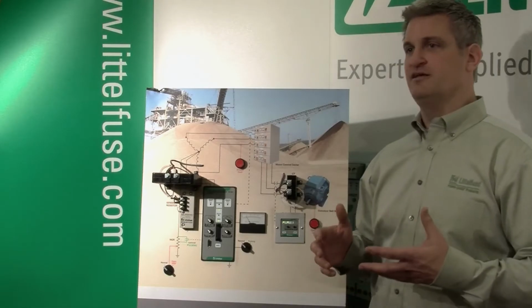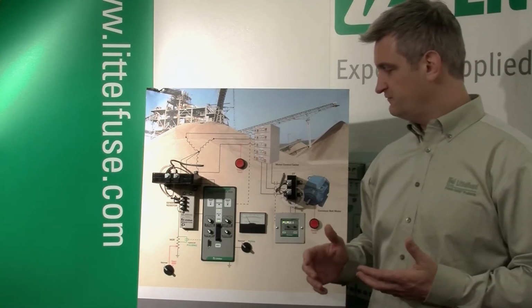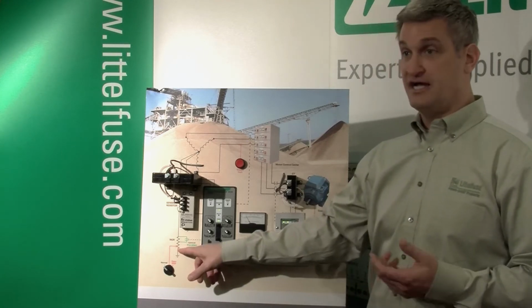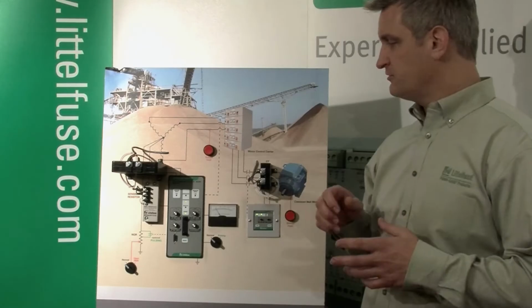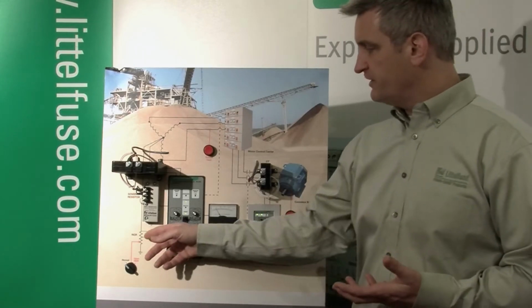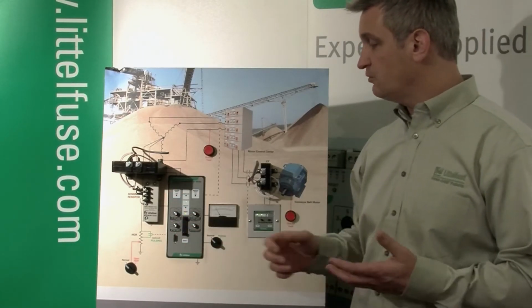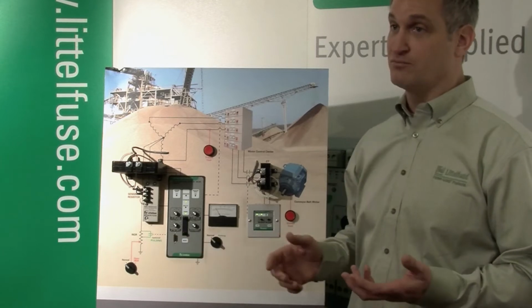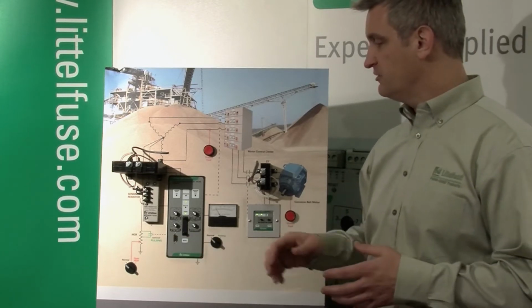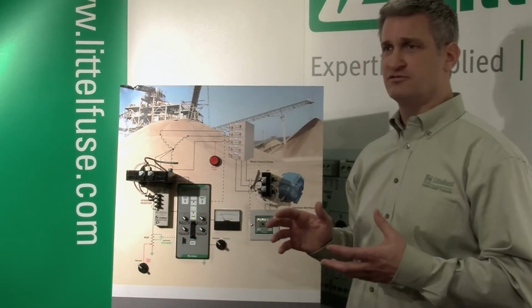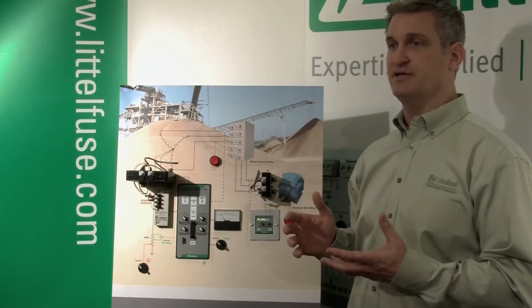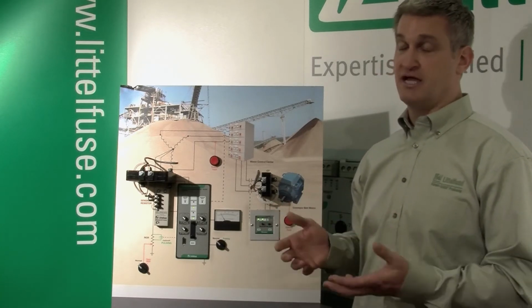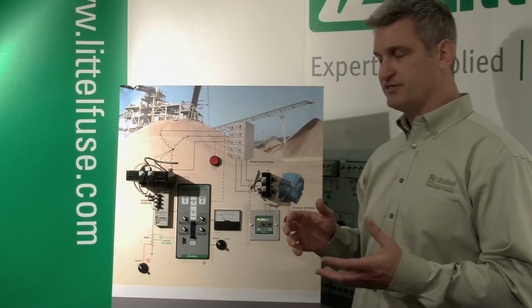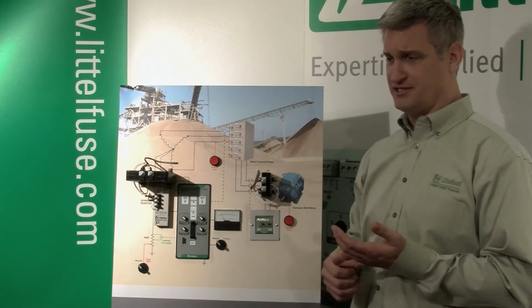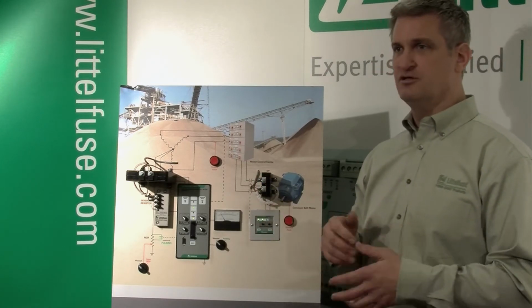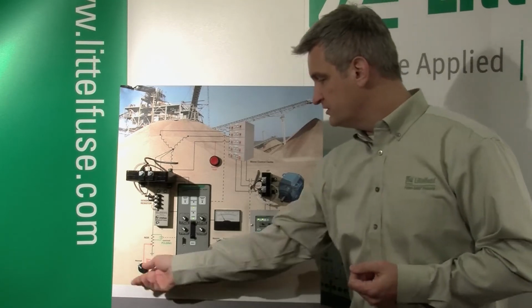Now that's great and all, but it only really works if that resistor remains intact. Actually, the whole circuit remains intact. You may think, well, what could go wrong? Well, resistors do fail. Sometimes there's a loose connection, or there could be a stolen wire. It happens more and more in North America. We're seeing quite a bit. When that happens, the system transitions from a resistance grounded system to an ungrounded system. And that brings a whole other set of safety issues, transient overvoltages, and inability to find a ground fault along with it. So here I'll demonstrate.